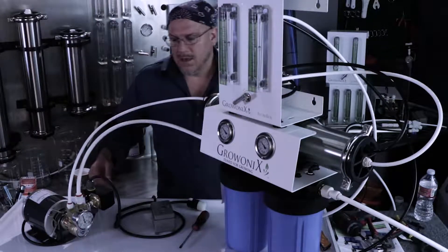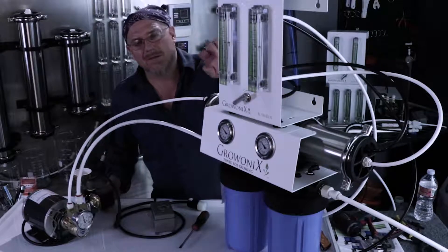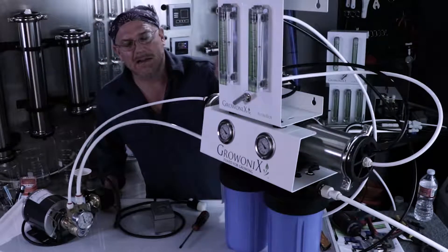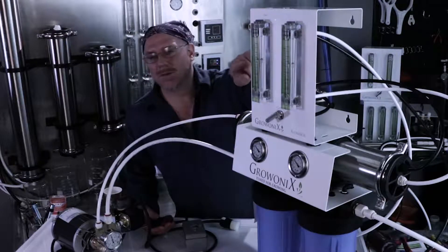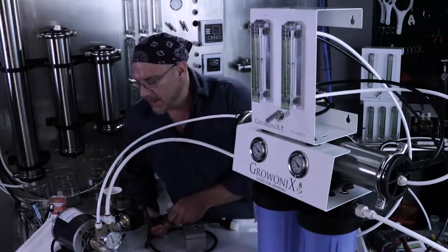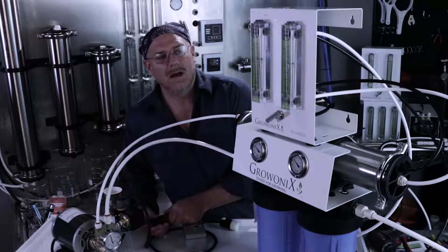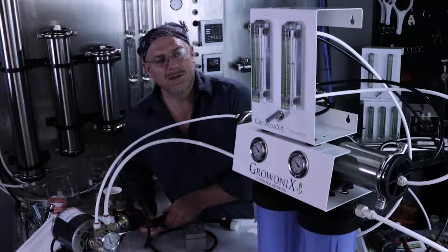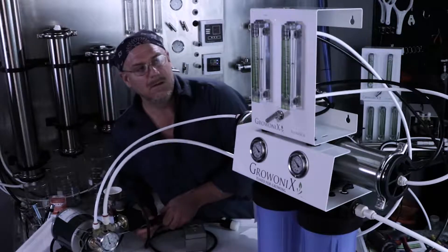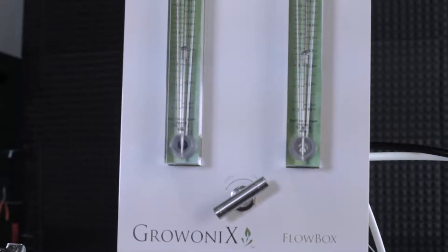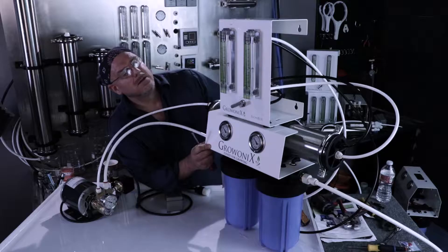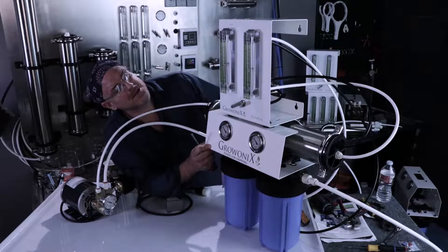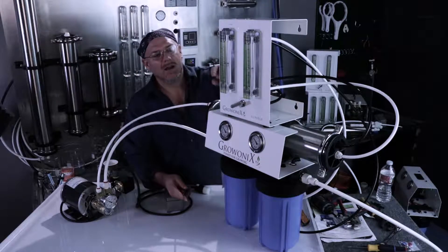You can see I wouldn't be able to know any of this stuff unless I had a flow box and I could read the flow meters and see accurately exactly how much water I'm flowing. Now I'm going to show you artificially, by turning the pump pressure down, how you can read this RO meter. Here's a brand new membrane in the middle of summer, and then six or seven months down the road, I notice my flow meters are much lower. I'm going to do this artificially by turning the pump pressure down. So now I moved from 1.2 gallons a minute down to 0.9 gallons a minute.